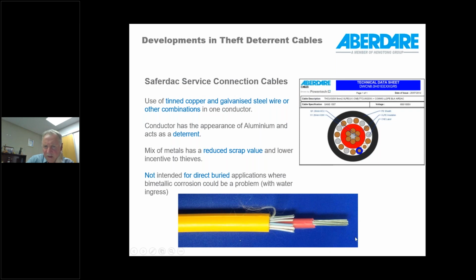You can see in this example, this photograph shows a cable with these mixed metals, and it has a look, let's say, similar to either galvanized steel or aluminium conductors, particularly for people who are not used to the look of these metals. So it certainly doesn't look like copper, and the mix of metals presents a problem for the thief and the scrap merchant to separate. And it's also not very clear what exactly the metals are that the thief would be bringing in for recycling. So Eskom has found this to be a significant help for them because of this reduced scrap value, and they've certainly seen that these cables have reduced the incidence of theft, particularly in new installations which make use of these type of cables.